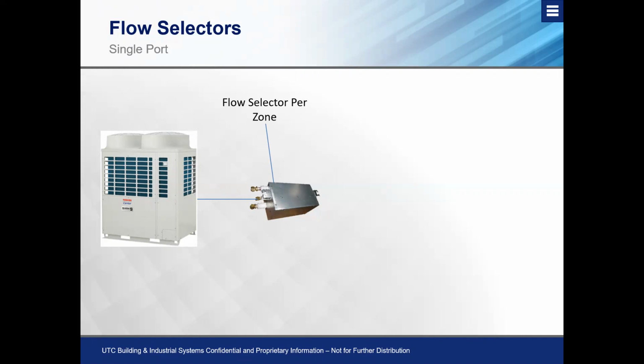Or if it's in cooling, we can only give you the liquid, boil it off into a suction gas, and then send it back. So, for example, if we have 3 indoor units connected on this one box, and let's just say the high wall unit that we have at the very top here is calling for heating, and it's calling for cooling. This system from the factory is set up as a heating priority. Now, this is configurable. You can set these for cooling priority depending on the physical location you're at. But as a general rule of thumb, these come set up as a heating priority, which means this unit up here is going to run for heat, while these 2 units down here are just going to sit and stand by, which is going to create some uncomfortable situations for the guys or girls in these particular areas. And it's important to know the system's not going to automatically switch over to run a cooling call for these.